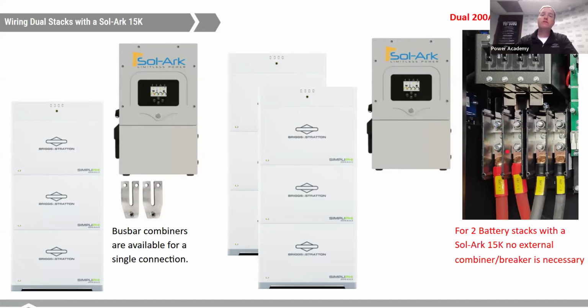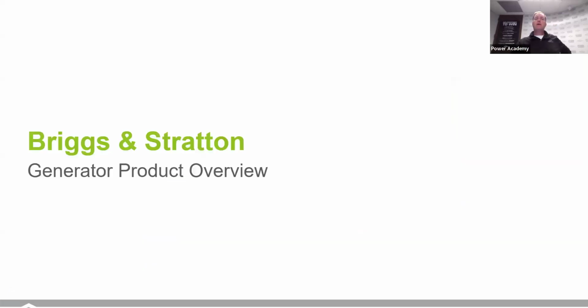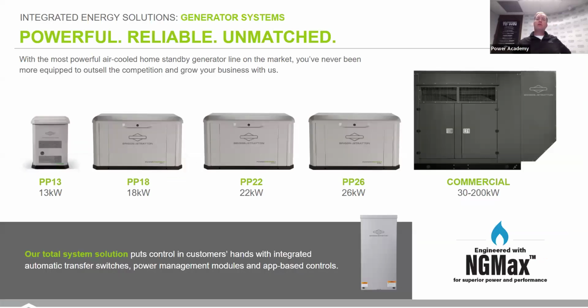You could also, and I've seen this done a lot, do a dual one-aught where you take two positives and two negatives off of one battery stack and feed them separately into the different bus bars here. What's also really nice is if you have a dual battery stack, like you see here in the middle with two 6.6 stacks of three, you don't need that Midnight Solar combiner, you don't need that Victron combiner. The Sol-Ark 15K pulls it in right there. We're seeing this a lot on the other hybrid inverters coming to market, where they have those dual battery inputs. Mike, any questions before we move on to generators?